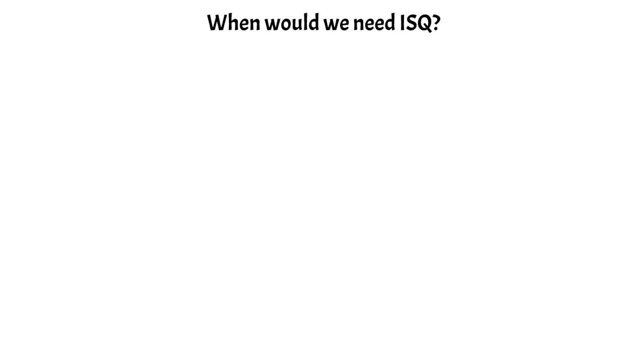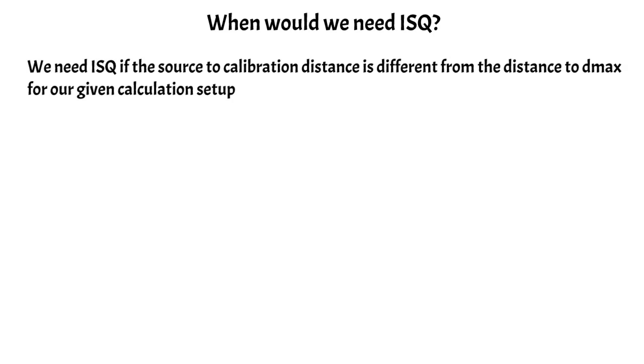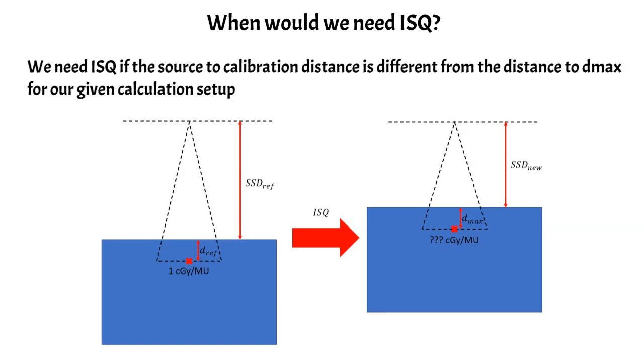So when might we need to use something like an inverse square correction? Remember, ISQ stands for our inverse square factor in our PDD dose calculation formalism. And we would need an inverse square factor if the source to calibration distance was different from the distance to D max in our given setup geometry. And so this is an illustration showing what I mean by this.